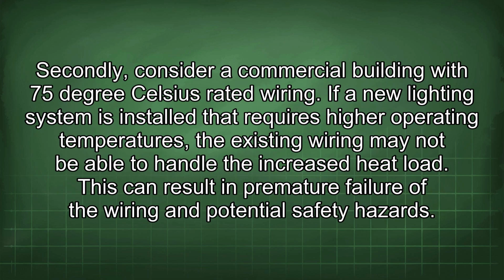Secondly, consider a commercial building with 75 degrees Celsius rated wiring. If a new lighting system is installed that requires higher operating temperatures, the existing wiring may not be able to handle the increased heat load. This can result in premature failure of the wiring and potential safety hazards.